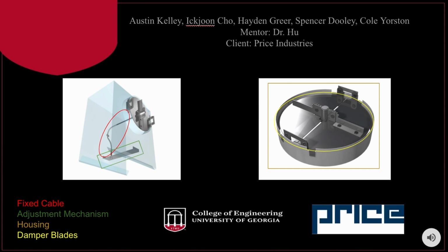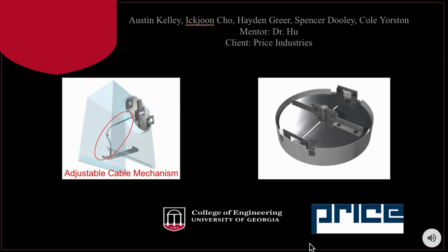The original VCRA EC damper is made primarily of in-house sheet metal material, and the overall structure can be decomposed into 4 parts: the fixed cable, the adjustment mechanism, the damper blades, and the housing. The current design uses a flexible cable which is composed of multiple parts including a spring, a worm gear, cotter pins, and more. For adjustment of the damper, the customers have access to a screw which rotates the cable, rotating the worm gear at the end, which ultimately opens and closes the damper blades. This design has remained popular among consumers over the years for its reliability and ease of adjustment.